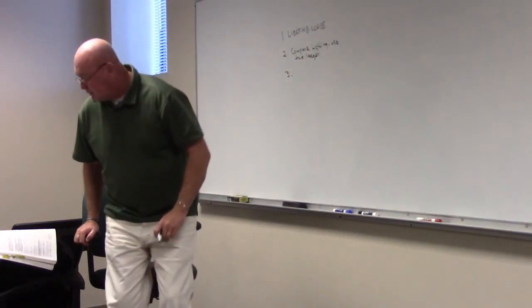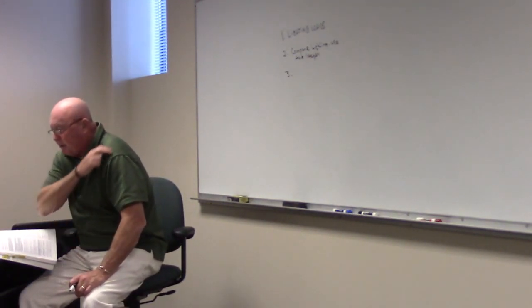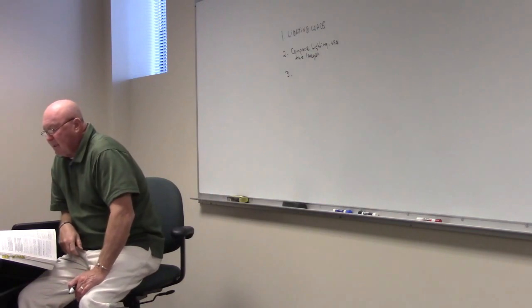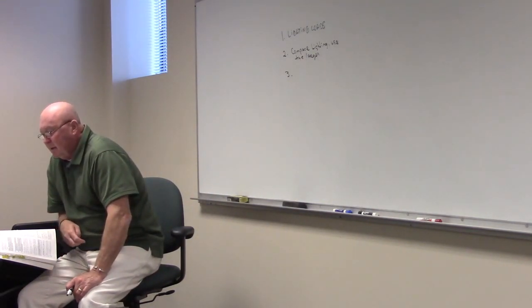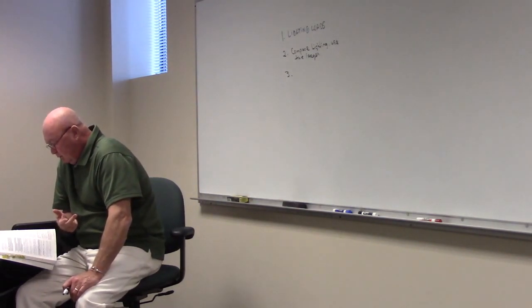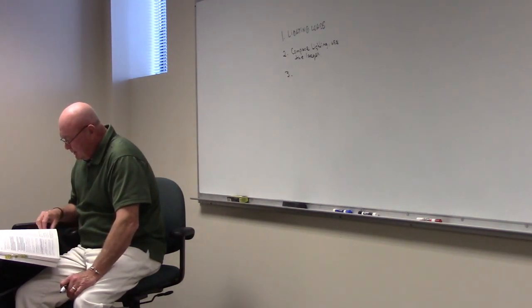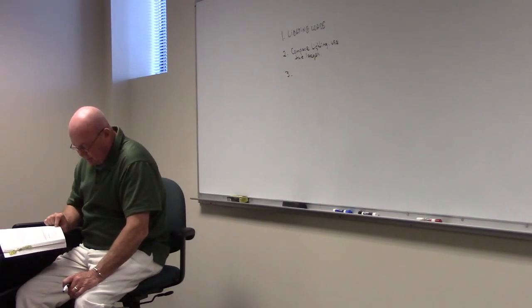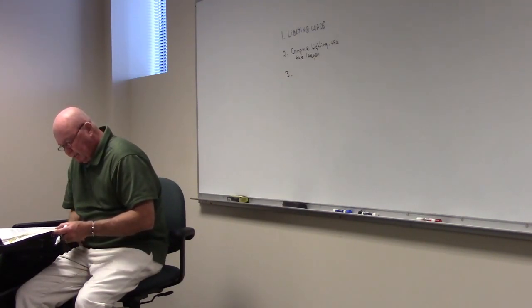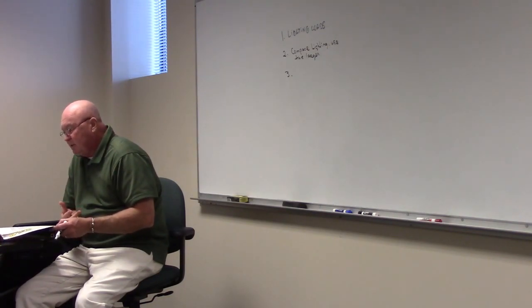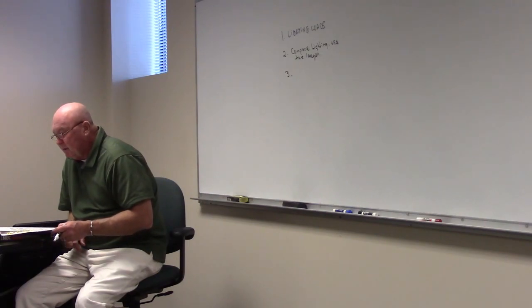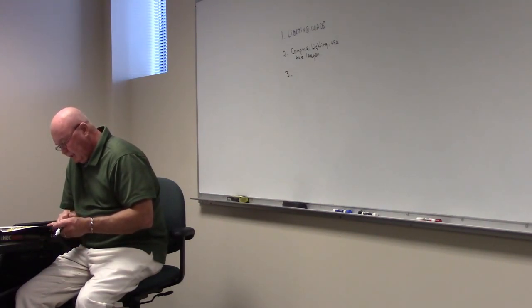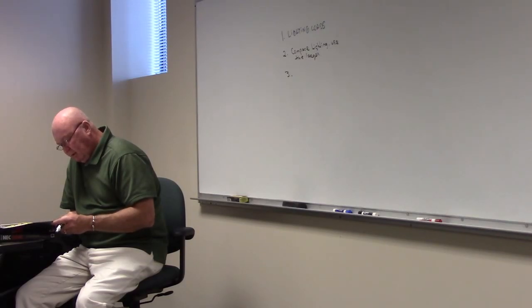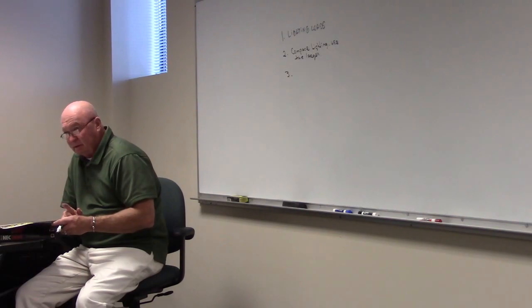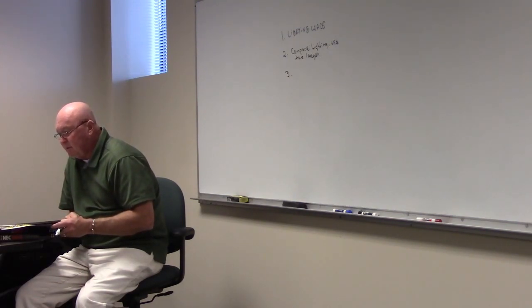All right. Step number 3, calculate the lighting loads used for other than general illumination, such as task lighting, exterior lighting, accent lighting. Refer to the applicable sections; we can look at 220.14(D). An outlet supplying a luminaire shall be calculated based on the maximum volt amps of the equipment and lamps. So you're just using the actual load there. 220.14(E) talks about heavy duty. Outlets for heavy duty lampholders shall be calculated at a minimum of 600 volt amps. Okay, so that's something to remember.